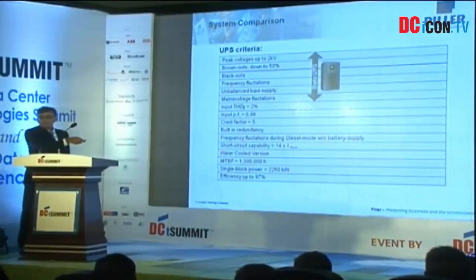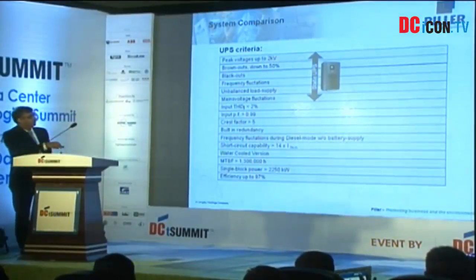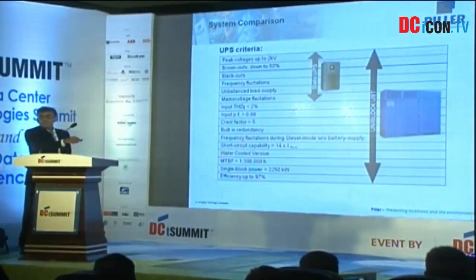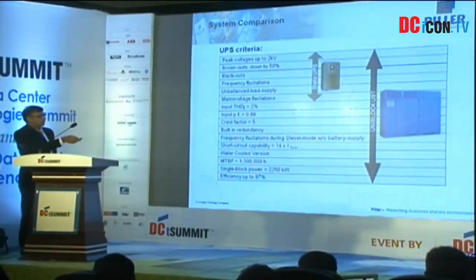So this is a very important slide to compare the coverage area of a static UPS against a rotary UPS system. These are the criteria which UPS have to meet. Static UPS covers from here up to here, whereas a UBT plus system or a diesel rotary UPS system covers all the way from here up to here, including very high efficiencies.